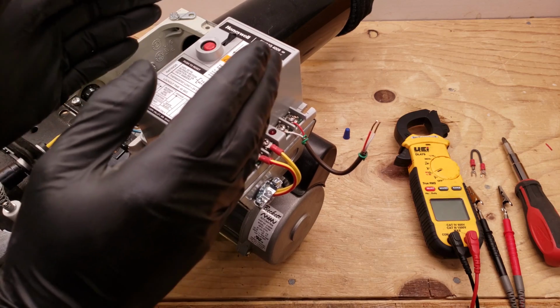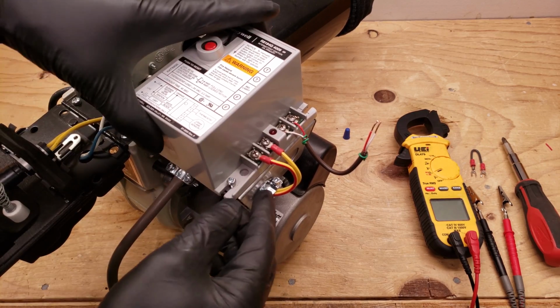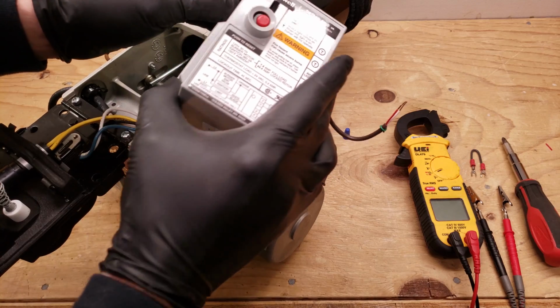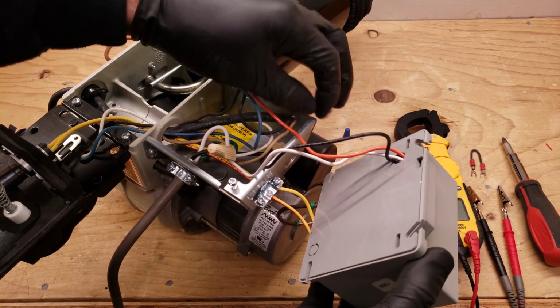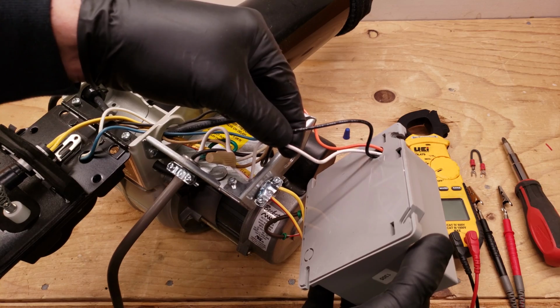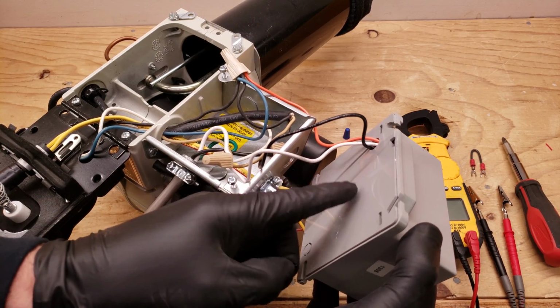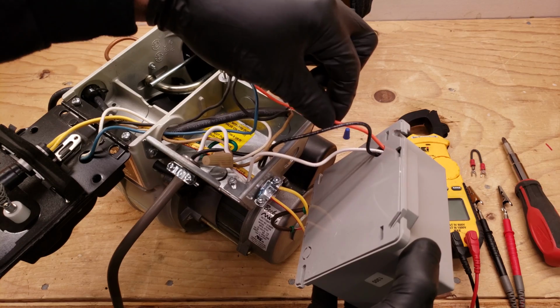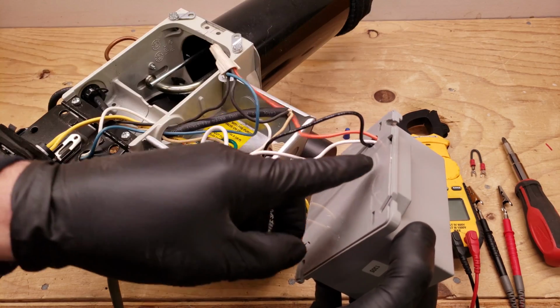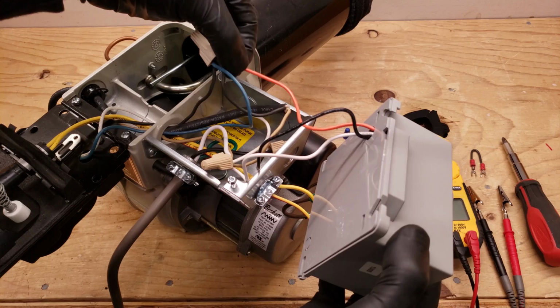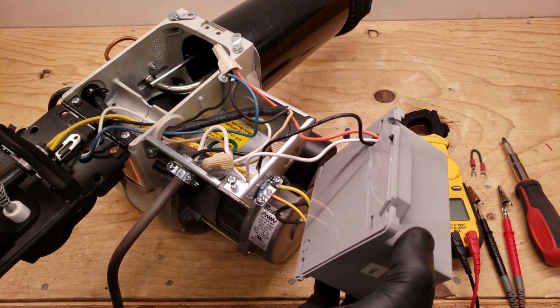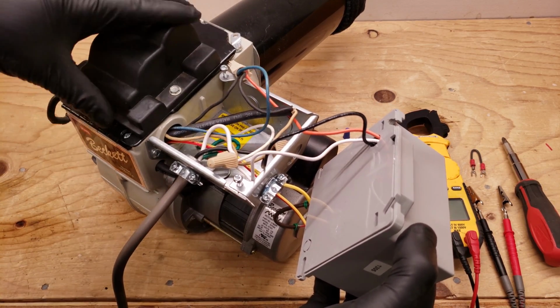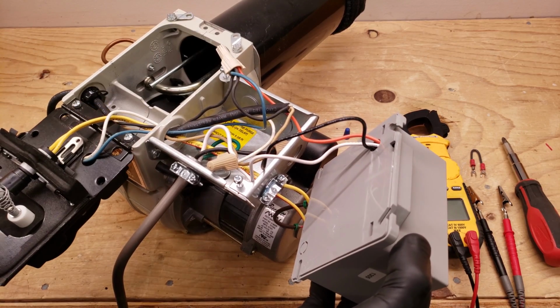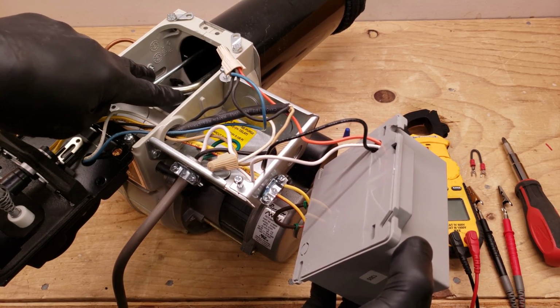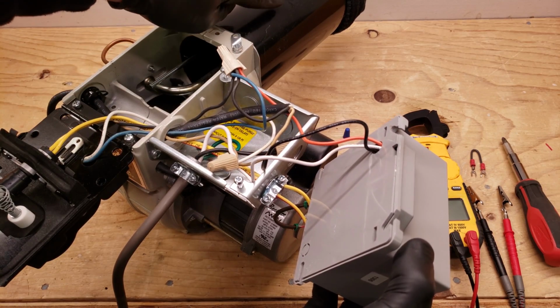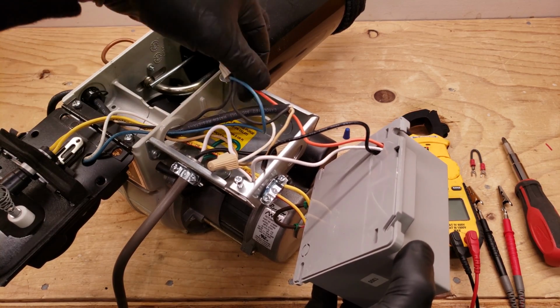So how the primary control works is it has some power wires. Your white and black right here, that's your power to the primary control. Your orange is the output. So when it's sending a signal for this oil burner to light, it's sending 120 volts over to this transformer right here. This is an electronic transformer, and it's going to put 20,000 volts right onto these two rods. And in the front up here is where it's going to ignite the oil. So that's one of the wires.